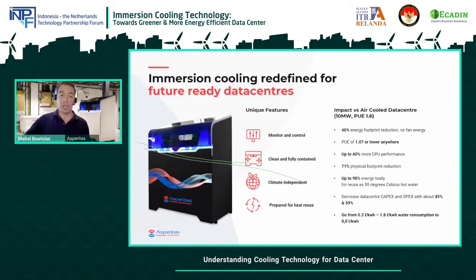So instead of chillers and other cooling solutions, dry coolers are a great solution for immersion cooling, data centers — it's all we need. That translates to a much lower PUE, higher hardware performance, less space required, a great business case, and no water consumption, as mentioned. I think this is a great case in comparison to most data centers practically built in the region now. Immersion cooling can drastically change that if it were adopted.